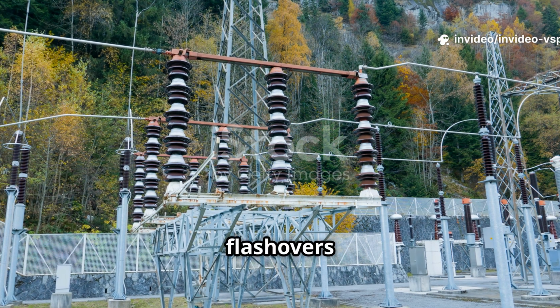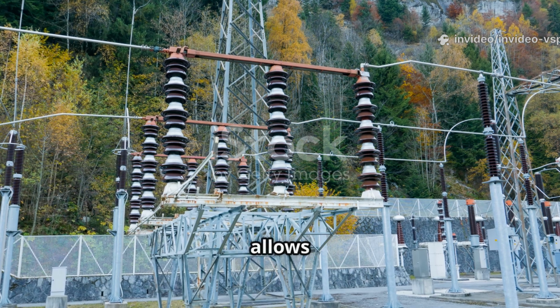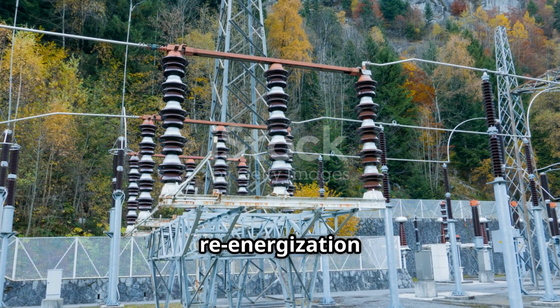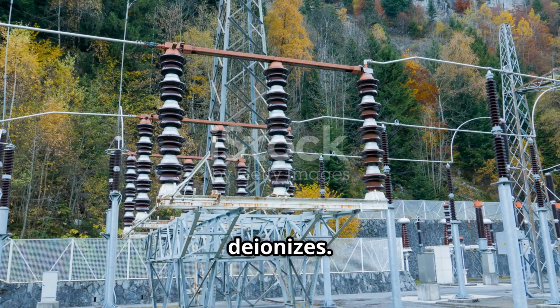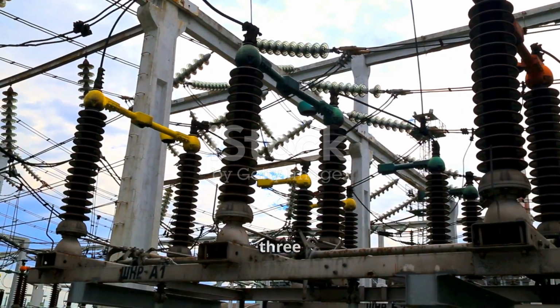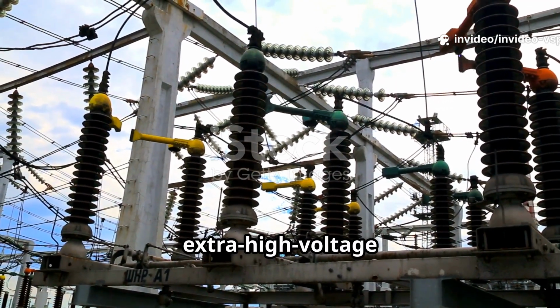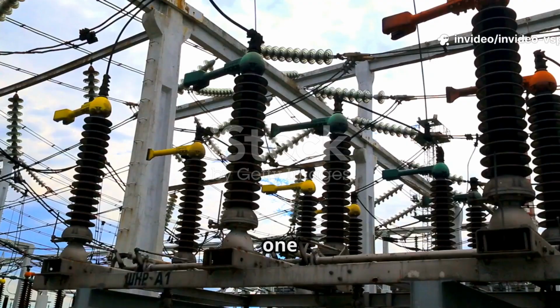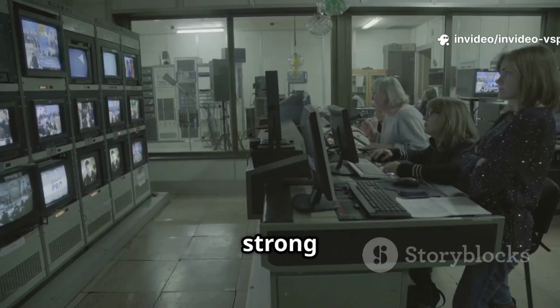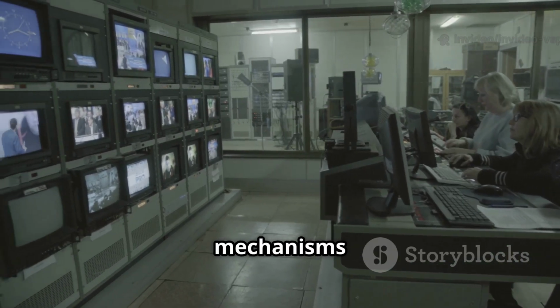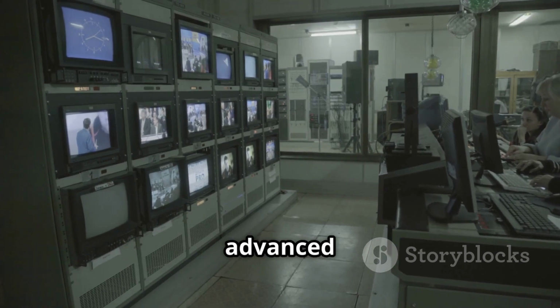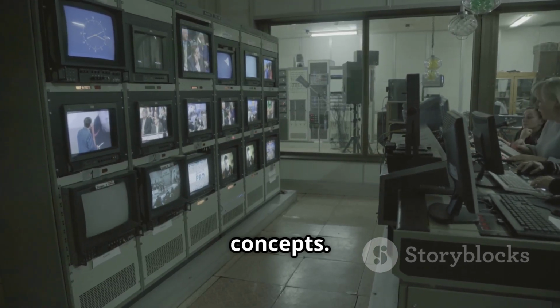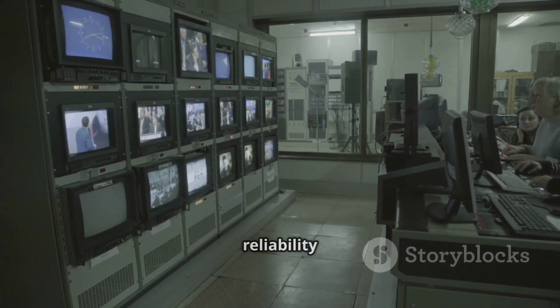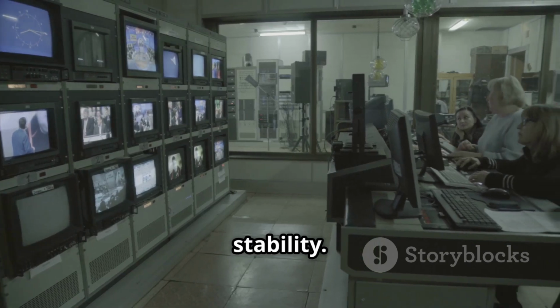Many faults like flashovers are temporary. Reclosure allows automatic re-energization after the arc path deionizes. Low voltage systems allow up to 3 reclosures, while extra high voltage systems typically permit only 1 due to stability risks. A strong understanding of these protection mechanisms is essential before moving into advanced substation design concepts. These basics enhance system reliability and maintain grid stability.